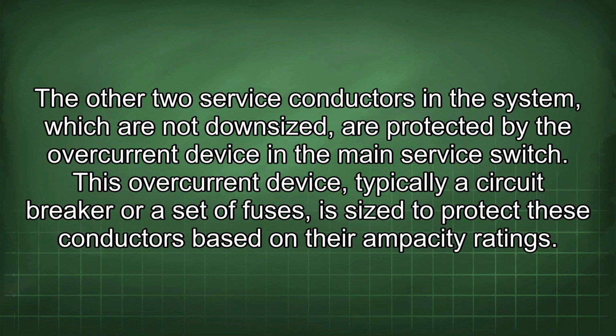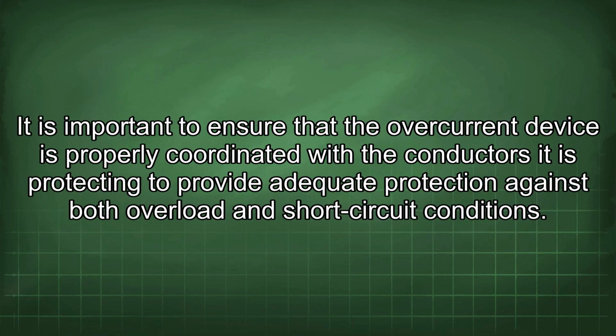The other two service conductors in the system, which are not downsized, are protected by the overcurrent device in the main service switch. This overcurrent device, typically a circuit breaker or a set of fuses, is sized to protect these conductors based on their ampacity ratings. It is important to ensure that the overcurrent device is properly coordinated with the conductors it is protecting to provide adequate protection against both overload and short-circuit conditions.